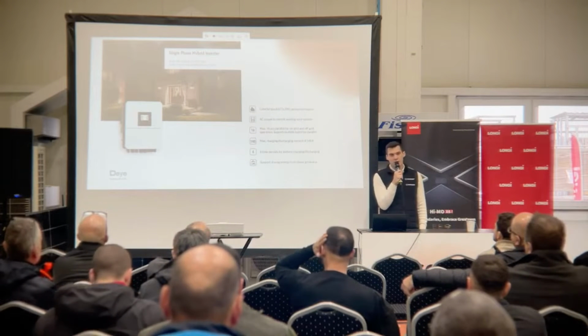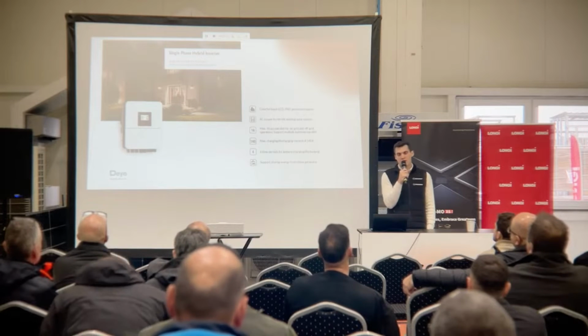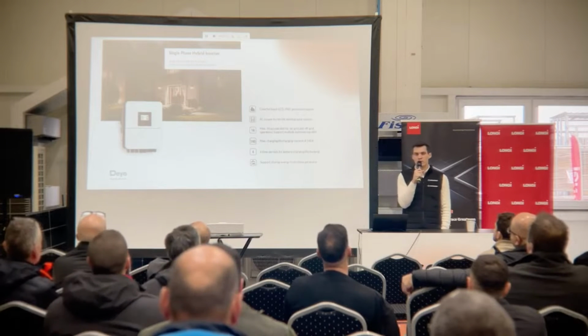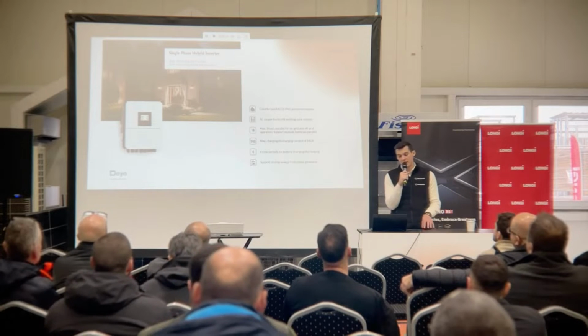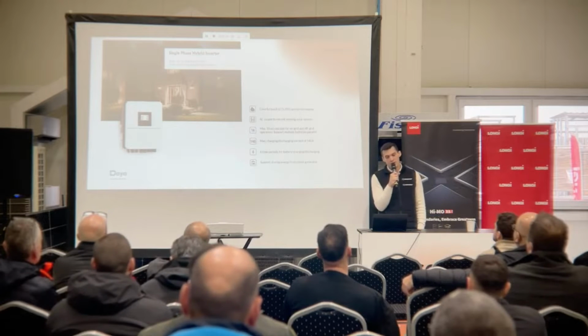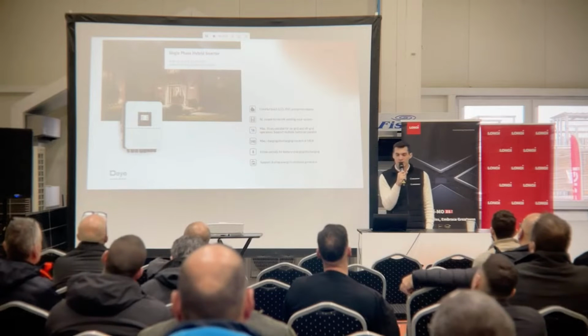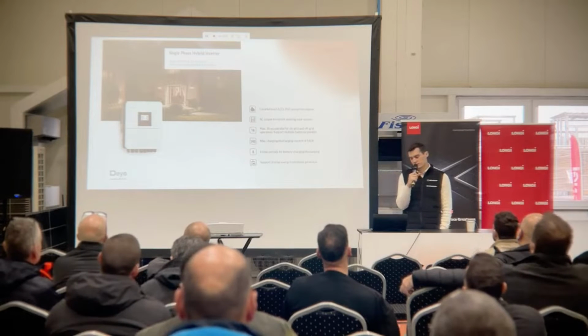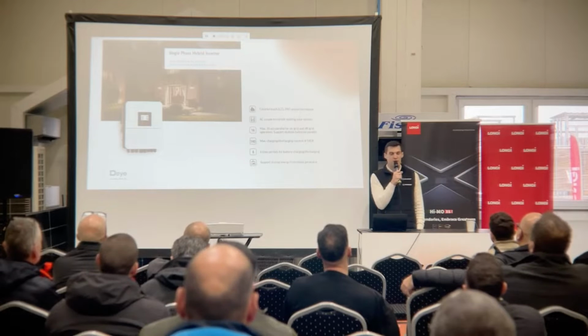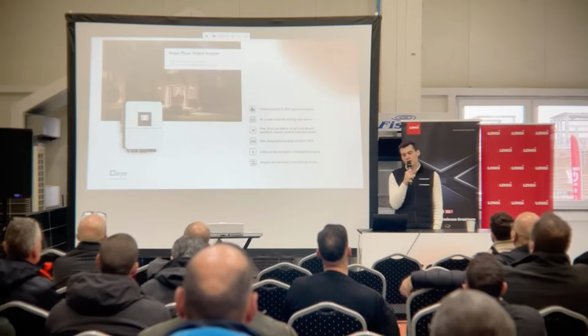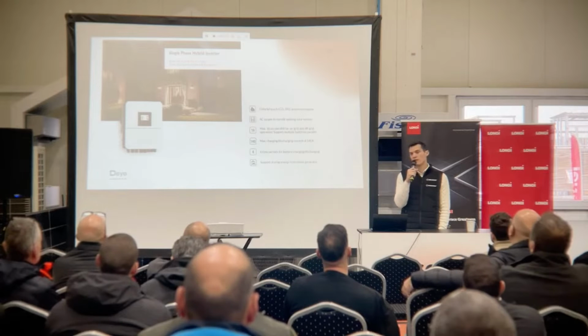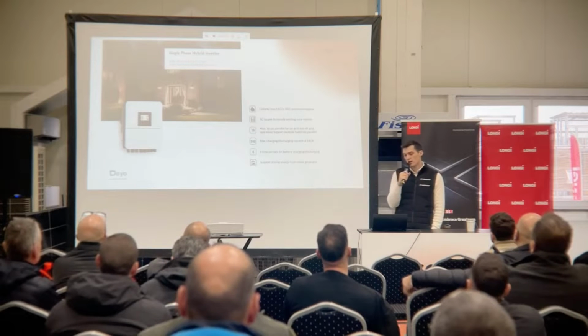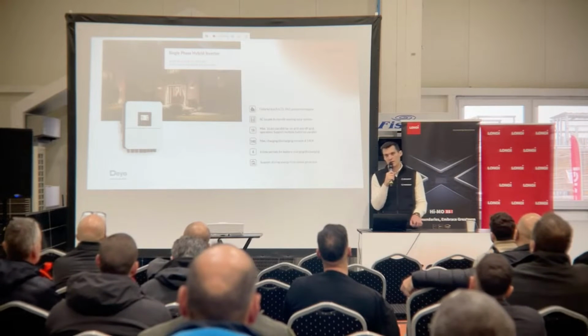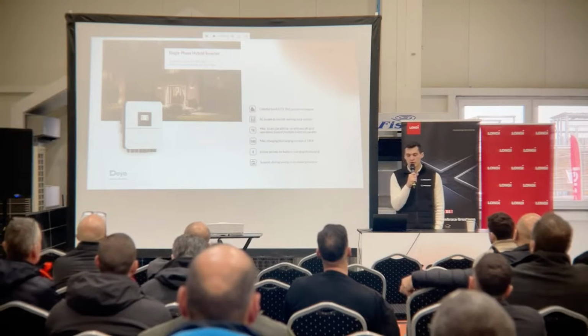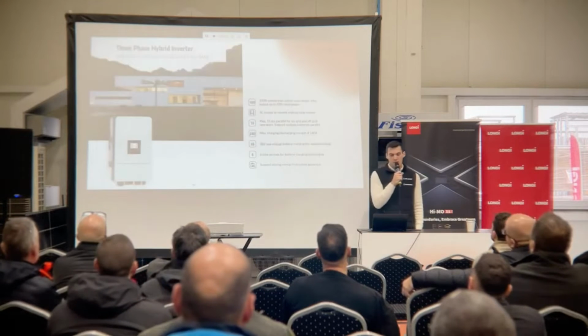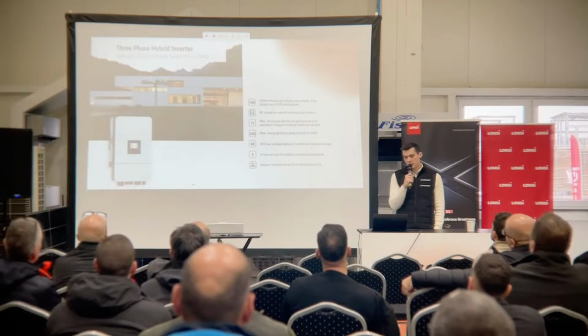Basically, when we recommend one-phase, it's mostly for applications where you'd like to do an island installation, because even if the three-phase inverter is an asymmetric one, if all your consumers are on one phase, a one-phase inverter can surely power those consumers. Meanwhile, with a three-phase inverter, you have to do some thinking and grouping of the consumers so the system works correctly. There is also the new hybrid three-phase one.